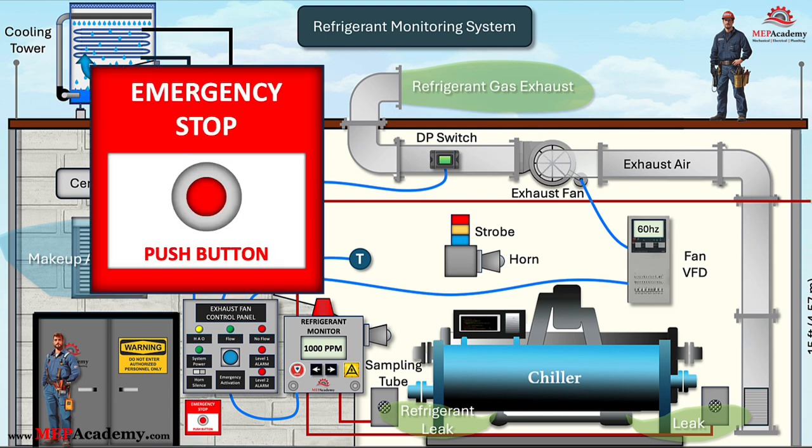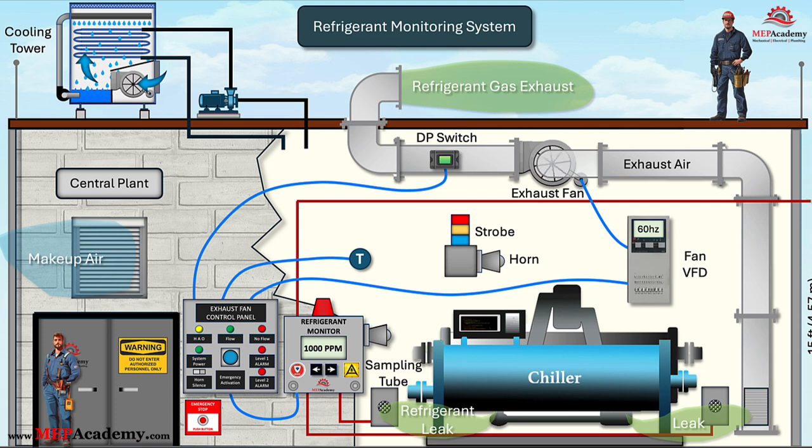Emergency off-only control switch requirements for chiller rooms: to ensure safety in refrigeration machinery or chiller rooms, an emergency off-only control switch must be installed immediately outside the primary exit of the room. This switch must be of a break glass type or have a protective cover, preventing accidental activation while ensuring quick access in an emergency. This requirement applies regardless of the refrigerant type or electrical system used. The primary function of this emergency switch is to shut off critical refrigeration equipment — including refrigerant compressors, refrigerant pumps, and normally closed automatic refrigerant valves — and to activate audio and visual alarms, helping prevent continued refrigerant leakage or system overpressure.